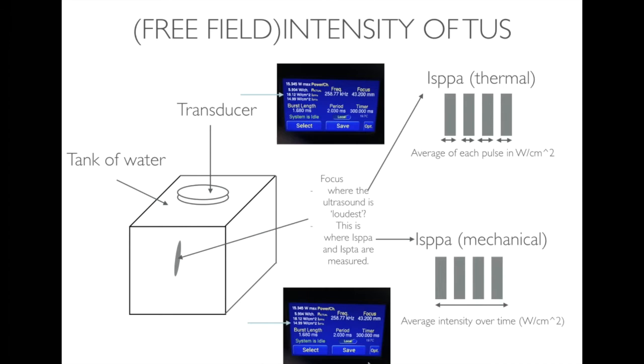There are more or less two common ways of measuring the intensity of ultrasound, in addition to a couple of other indexes I'll cover later on. One is called ISPPA, which stands for Spatial Peak Pulse Average Intensity. It's measured within that focus region I pointed to with my tank of water, and it's the average rate of energy absorption in watts per centimeter squared, averaged across pulses. That's generally used to measure heating, and it's the one that's most relevant to the safety of ultrasound in humans.